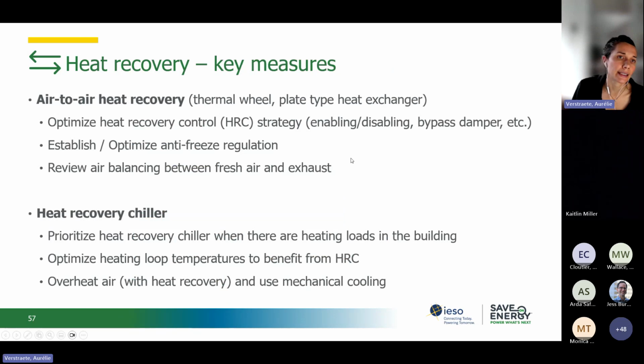To summarize the heat recovery opportunities, here you have air-to-air heat recovery. We discussed the thermal wheel, but it could also be a plate type heat exchanger. First, you want to optimize the control strategy: enabling, disabling, maybe bypass damper. You want to establish or optimize antifreeze regulation, and maybe review air balancing between fresh air and exhaust.